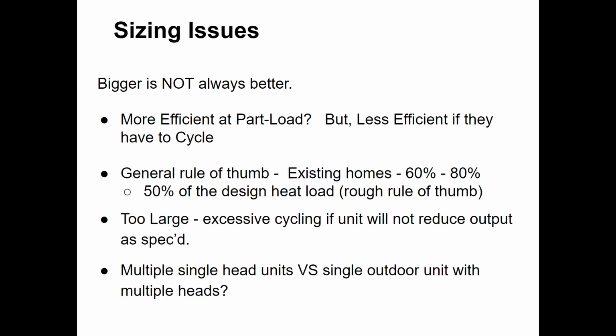There are tools and calculators and professionals who will help you do that analysis. But more important, if you put too big a unit in, it is constantly cycling on and off, even with those modulated units. What happens is that creates excessive wear on the equipment and it will start to perform less well over time. So when in doubt, go more low capacity than you think you need when you analyze your bill.